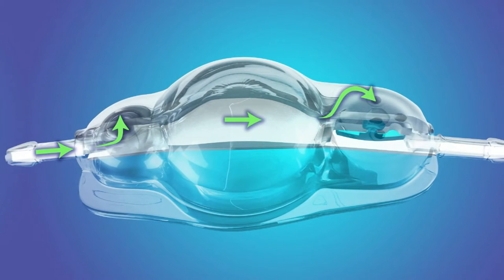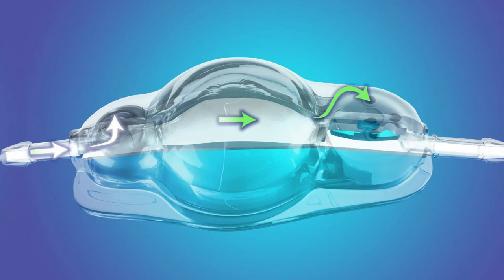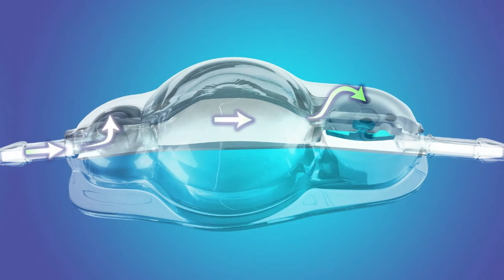As CSF flows through the contoured valve, it enters the inlet connector, flows by the proximal occluder into the central reservoir. For sampling CSF, the reservoir dome can be accessed using a 25 gauge or smaller non-coring needle.